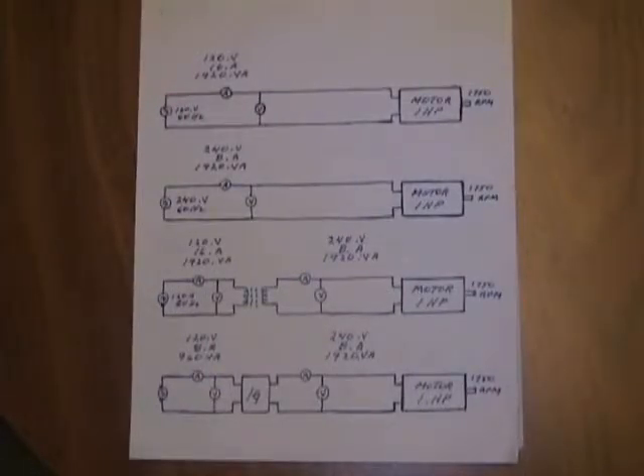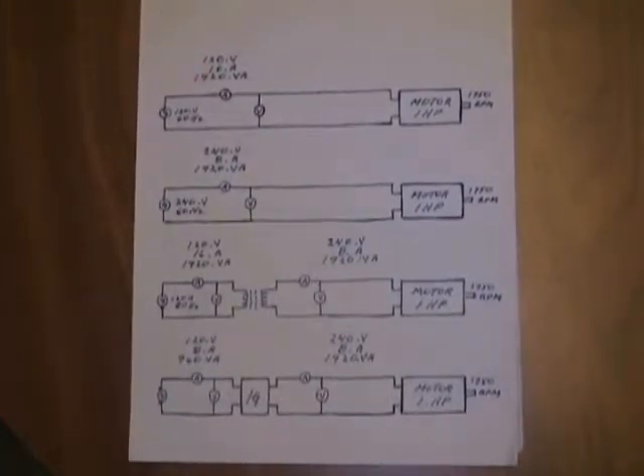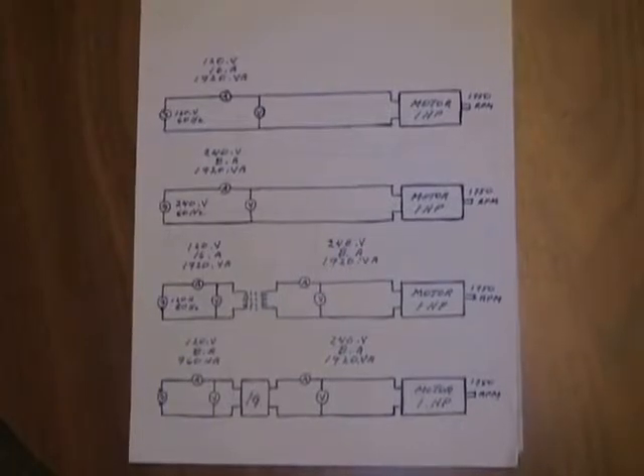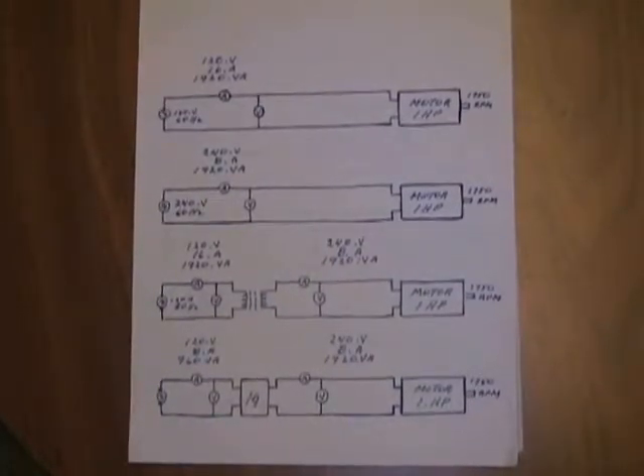When it is connected in the low voltage connection, it will require 120 volts, 16 amps, and it will require the multiplication of these two, which is 1920 volt amps.